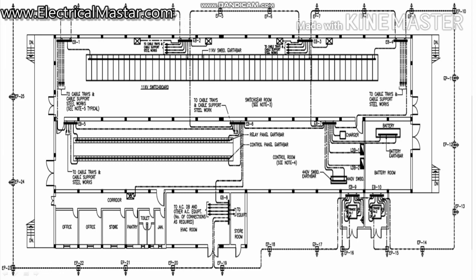Similarly for EB2, earth pit 4 and earth pit 5 are connected. From there it goes to the cable trays of the switchgear and the body of the switchgear, all the places. In a similar way you can take any earth bus bar. Any earth bus bar will be connected with 2 incomers, and it will go to a number of outgoing cables. And next significance: I told you the neutral of the transformer has to be connected separately. See here the earth pit number 15.